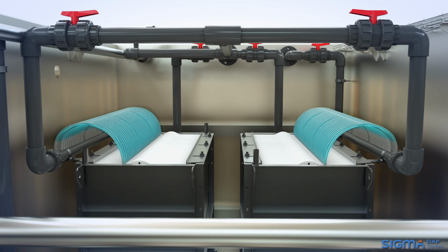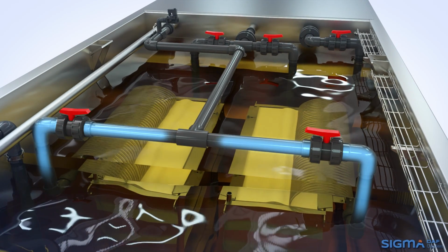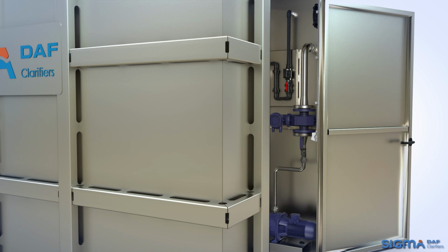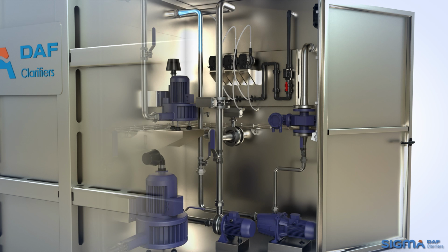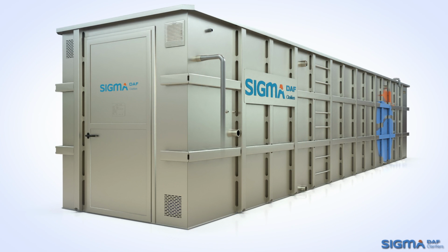The elements involved in the filtration process include the membranes and the self-priming pump. The latter produces filtered water free of solids, which is suitable for final discharge into a sewer system or natural watercourse. It is worth noting that by simply adding an ultraviolet disinfection process after filtration, water of a higher quality can be obtained, which can be used for sanitary purposes, irrigation, and similar processes.